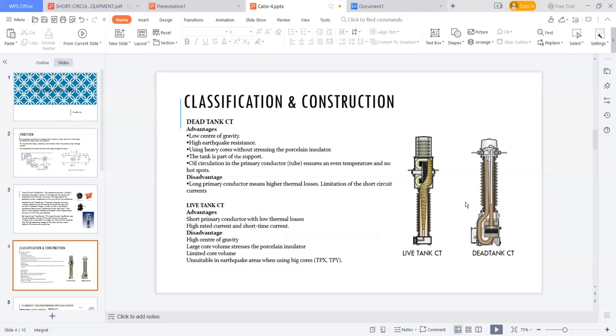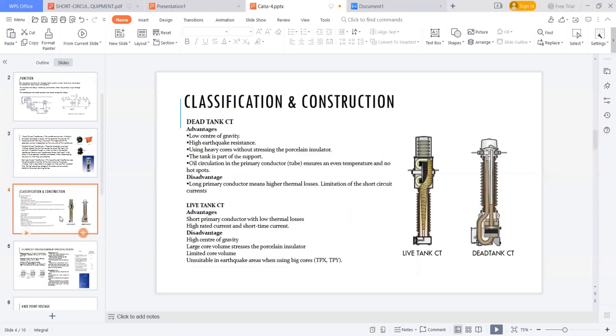Most cases, in all the cases, mostly we are using live tank CT because we are much more concentrating on high rated currents and short time currents. These are the installation kind of thing. Earthquake, not much. It's limited to some zones. And core volume stresses on insulator, we are choosing obviously good cantilever strength of the insulator to maintain this. So most of the projects, most of the projects, they are having the live tank CTs. So this is about just a classification of CTs.